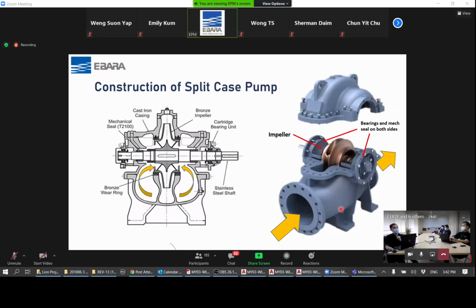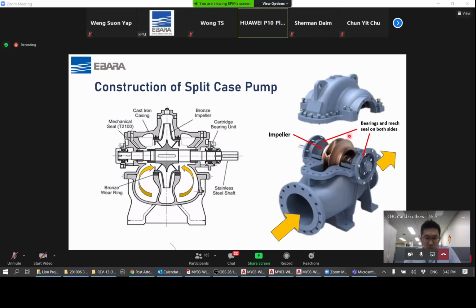Now, the next pump that we will talk about is what we call the split case pump. Now, you often have heard this term split case. Now, basically, as you can see from here, what it simply means is that the casing of the pump can be taken out, or rather split by half. Not by half, but rather the top part can be opened up to get access to the internal elements of the pump. Now, split case pumps are usually for medium to large flow applications.